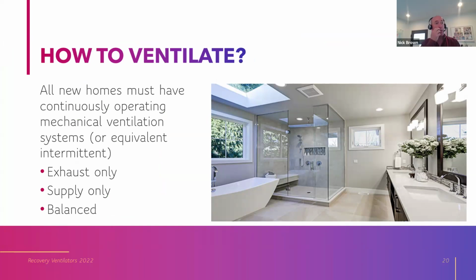All right, so most new homes, which are required to have continuously operating mechanical ventilation, do it something like this, with an exhaust fan in a bathroom running continuously. The energy code recognizes these roughly as equal approaches: exhaust ventilation, supply ventilation, where you're blowing in from outside a certain CFM, and balance ventilation, a combination of exhaust and supply ventilation running at the same time. That keeps neutral pressure in the space, but it uses more energy because you've got 2 fans operating concurrently.